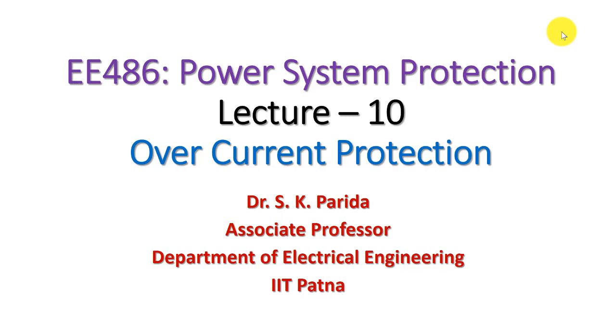So in this lecture we'll see the implementation of the inverse definite minimum time relay, the IDMT relay, and also talk about the advantages of the directional overcurrent relay. Then we'll talk a little bit about how the directional overcurrent relay can be implemented. Okay, let us start.